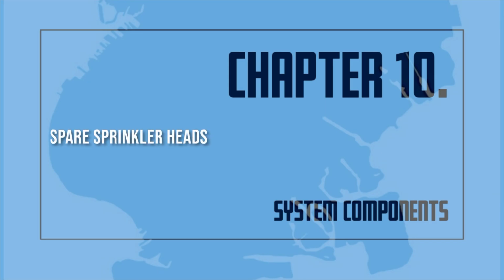Spare sprinkler heads. Sprinklers required for emergency replacement must be representative of the type of sprinklers installed, along with the proper wrenches. These wrenches shall be provided in the spare head cabinet. It is critical that sprinklers be replaced with devices that will perform similarly to the original system sprinklers. Sprinklers that are replaced during an emergency by unlicensed individuals require that the devices used have been verified appropriate for the protected area by a master fire suppression piping contractor.